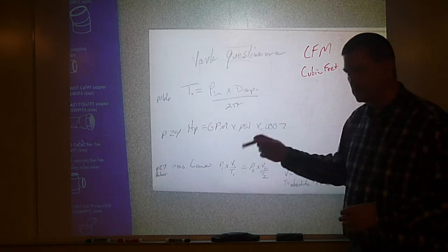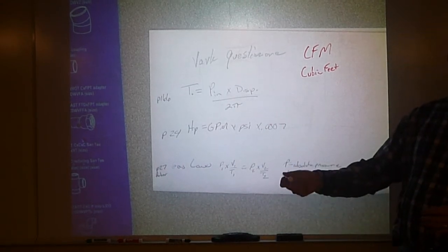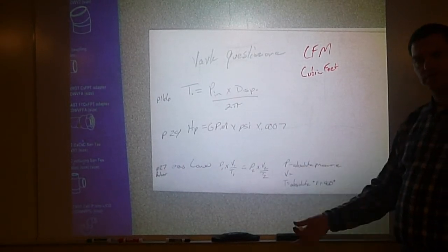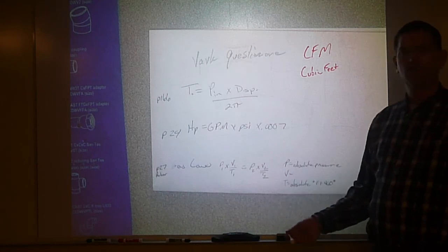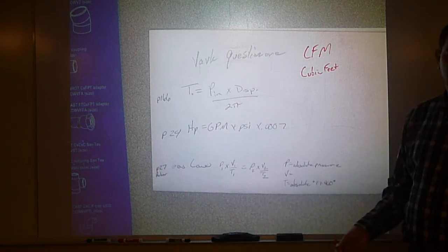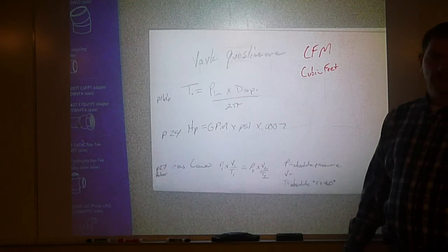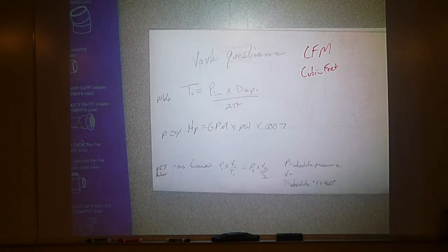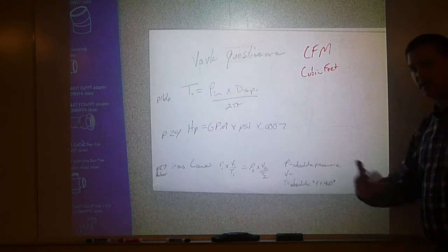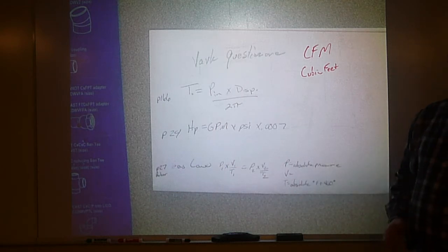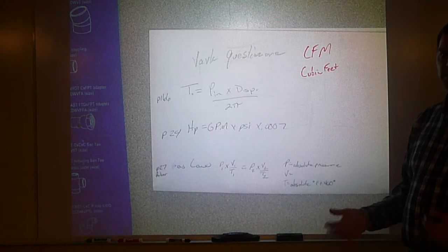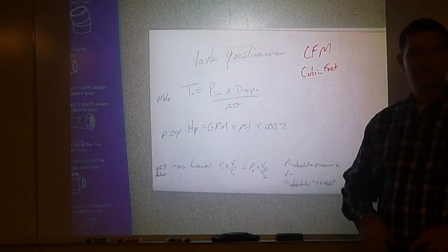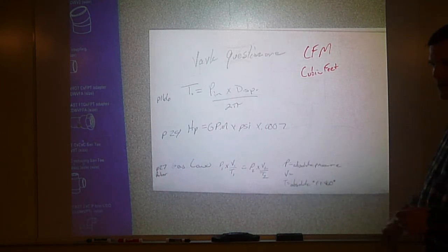So if your intake air is colder, it will require less free air. Hope that makes sense. If your outside incoming air is warmer, it's going to increase your free air delivery demand to make the same pressure and temperature on the outgoing side.